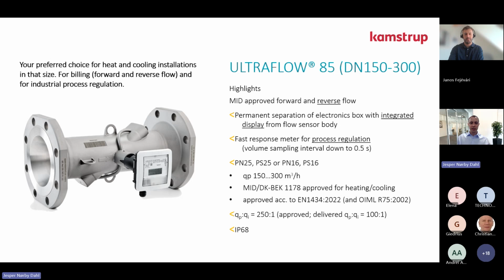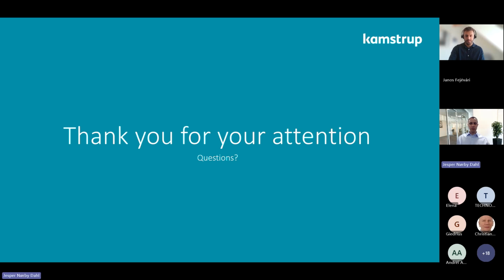It is tested according to the newest EN 1434 standard from 2022. And it's also OIML compliant. It is 250 to 1 approved, but we will deliver 100 to 1. And it's IP68 now, the complete flow sensor. This was a very fast brief into ULTRAFLOW 85.